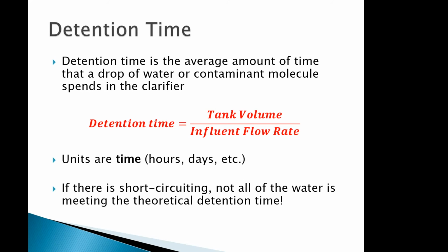So how could we use this information? I would say if you calculated detention time and your detention time is appropriate for what you're trying to achieve, but you find that the process is still not performing well, you might want to look at the geometry of the tank and short circuiting as a possible solution. Sometimes just installing a baffle in the tank to not allow water to short circuit, to force it to mix into the full tank, is all you need to do to really improve your performance. Okay.